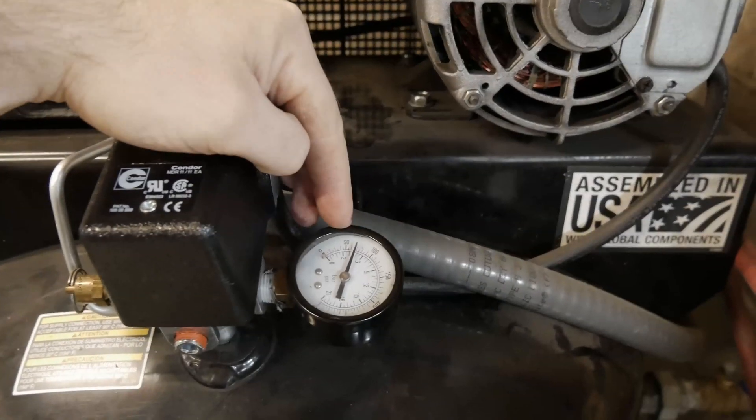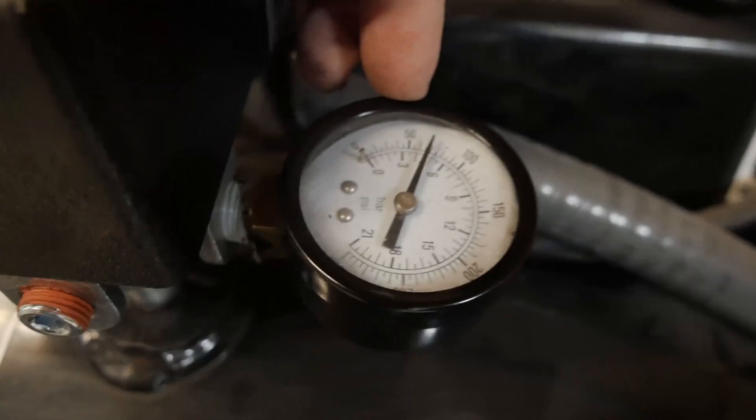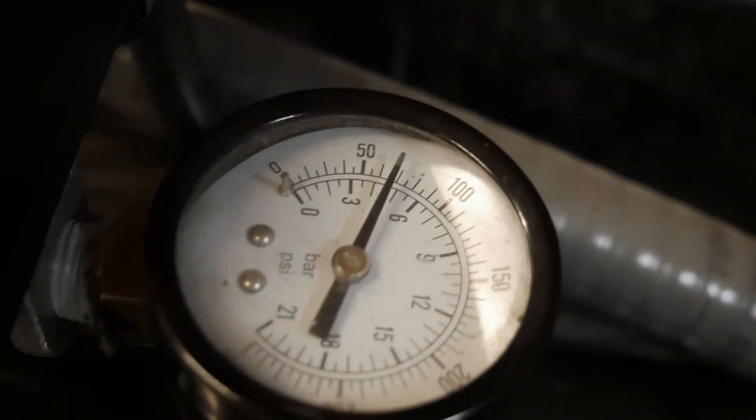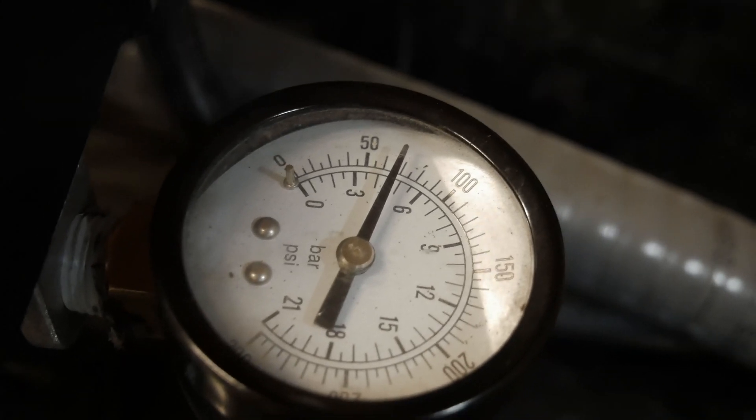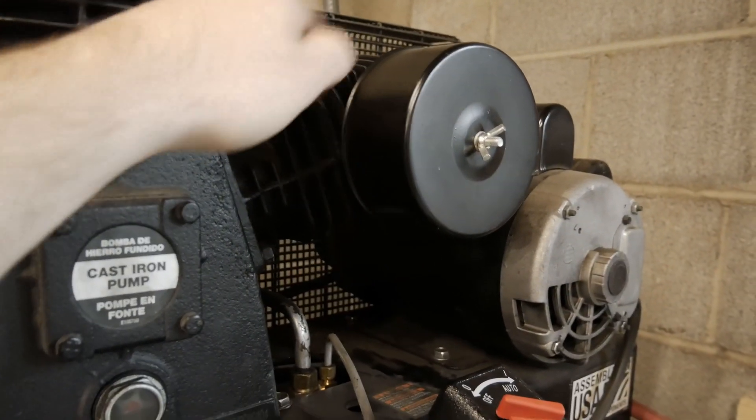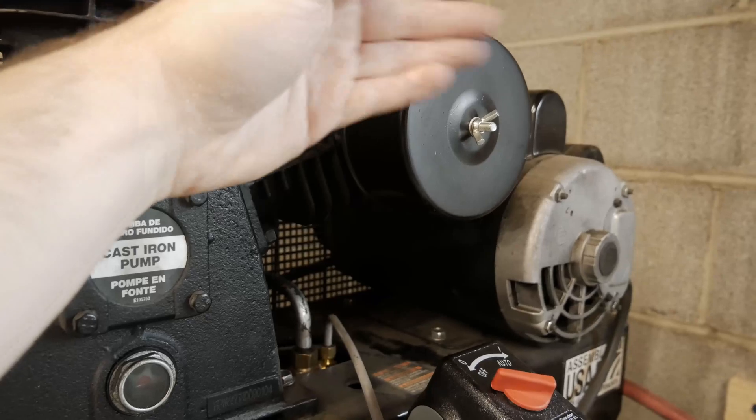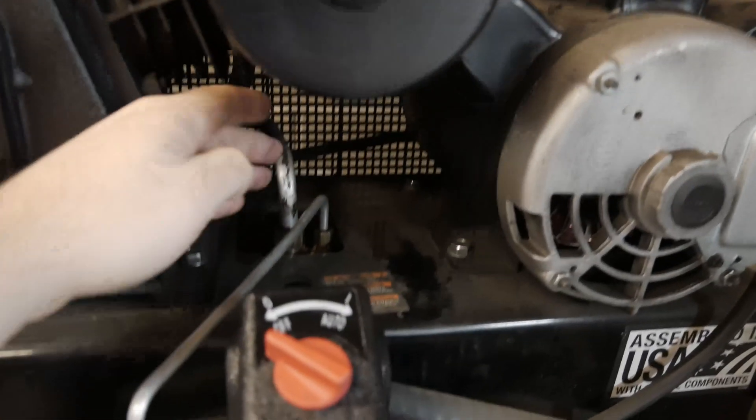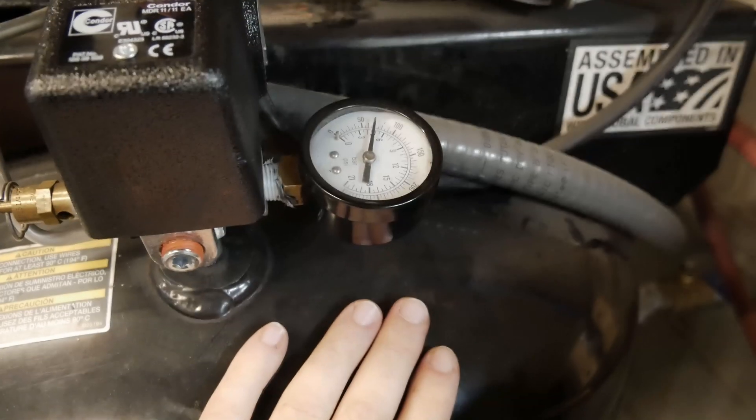Before when it was running we would stall out right around 50 to 75 psi and it wouldn't build any more pressure than that. That's because this cylinder right here was not actually building any pressure. As the piston went up and down it was blowing air in and out. It comes out of this tube, goes down through our check valve, and then you store pressure in your storage tank. So that process can't really occur with only two cylinders operating.